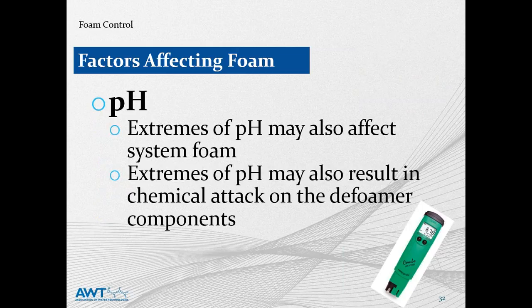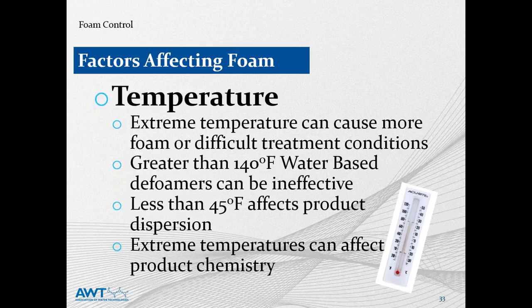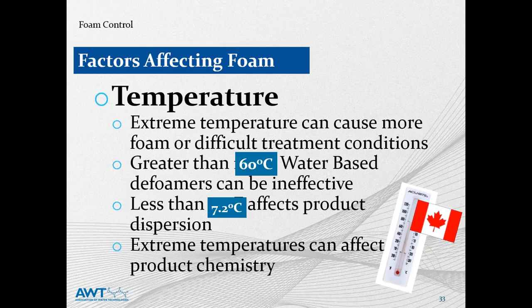When talking about pH, extremes of pH may affect the system foam and also the product performance itself — extremes can make the product much less effective. This is a slide Kevin and I had a good chuckle about. When talking about temperature, you need to consider how temperature will impact the foam and how it will impact the performance of the actual product. Temperature can cause the creation of more foam and can negatively affect product performance. At temperatures greater than 60 degrees Celsius, water-based defoamers can become less effective. At temperatures less than 7.2 degrees Celsius, it can actually inhibit the dispersion of the products. I insisted that Kevin put the Canadian temperatures in there.